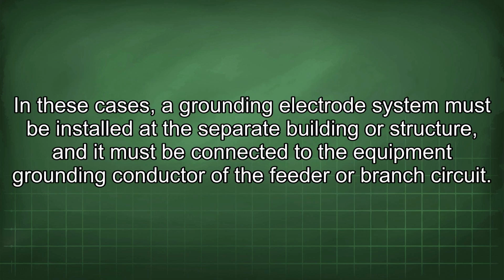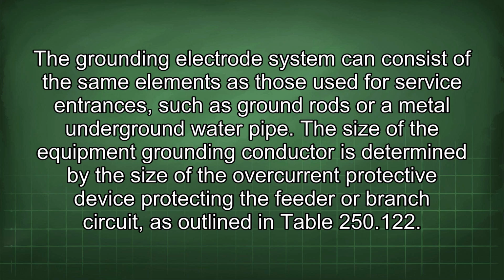Section 250.32 addresses grounding requirements for buildings or structures supplied by a feeder or branch circuit. In these cases, a grounding electrode system must be installed at a separate building or structure, and it must be connected to the equipment grounding conductor of the feeder or branch circuit. The grounding electrode system can consist of the same elements as those used for service entrances, such as ground rods or a metal underground water pipe.